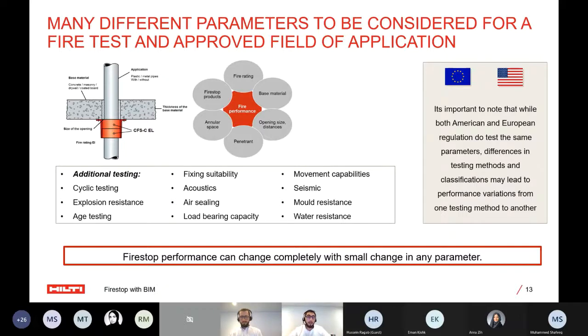In all the global standards, whether American, European, or others, any application on the job site needs a relevant or matching tested fire stopping system from an approved lab. In the UAE, the 2 approved global standards are the American system—ASTM or UL standards—and the European standards, referred to as EN codes and standards or EN approvals. These are the only 2 approved standards here in the UAE.